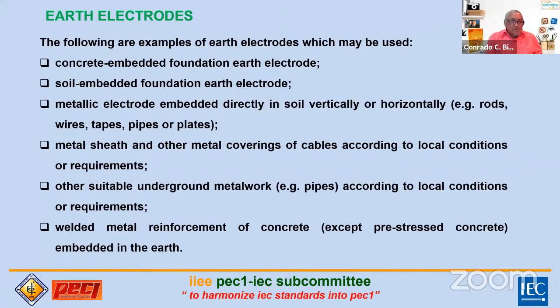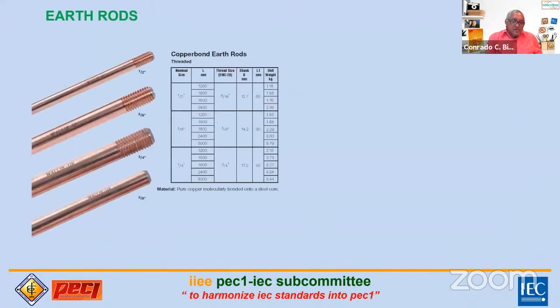Let's see some examples of earth electrodes, earth rods. This is a Copperbond that's actually steel but coated. There are product standards when it comes to earth rods, and manufacturers have to follow standards in manufacturing earth electrodes. You can't just install an earth electrode carelessly; the product quality must comply with specific product standards for earth rods.